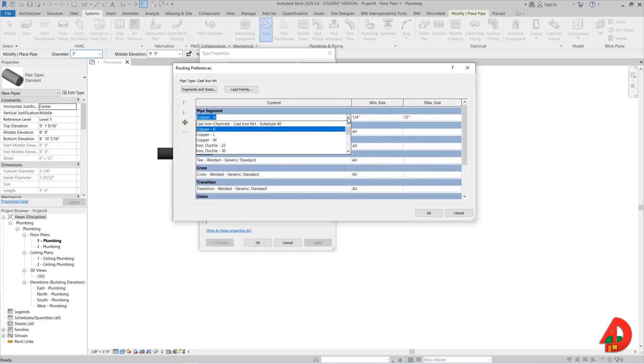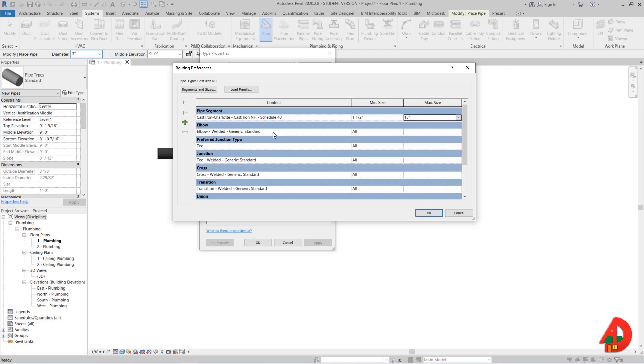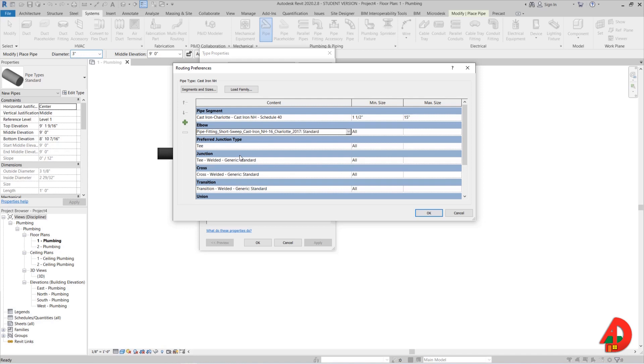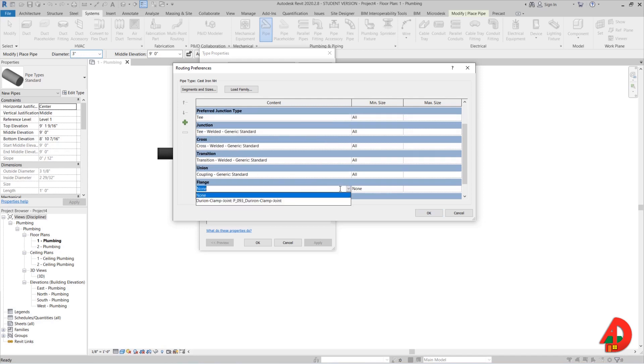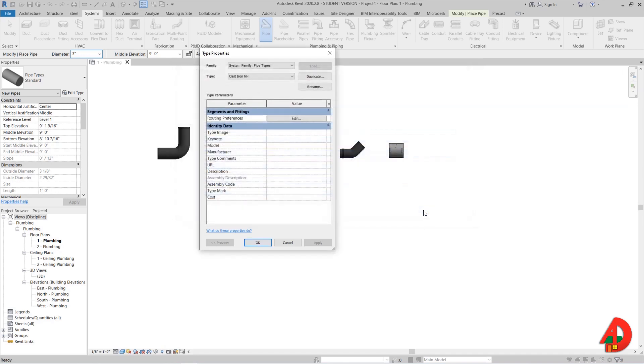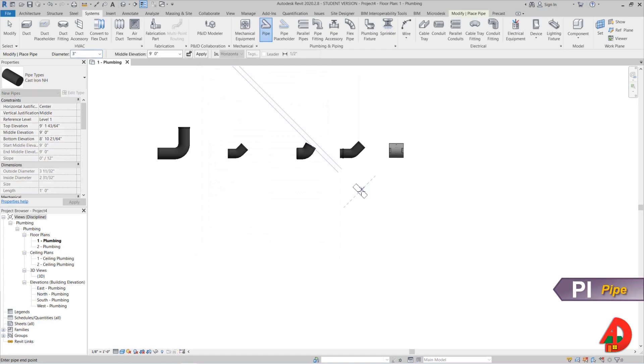Here under pipe segment I can select the cast iron schedule 40 that I just created earlier. The maximum size is 15 inches so I will also change that. For the elbows I will select the short sweep, and if I scroll down I will also be able to assign a clamp family for flange. Clamps are obviously not flanges, but this is how we can convince Revit to add a clamp at each end of a fitting.